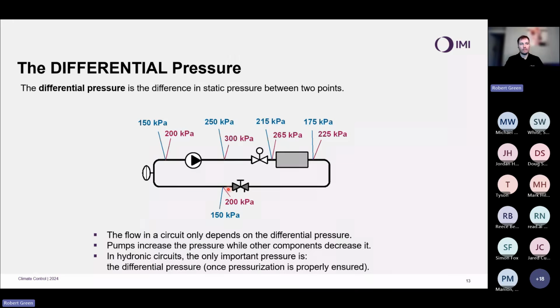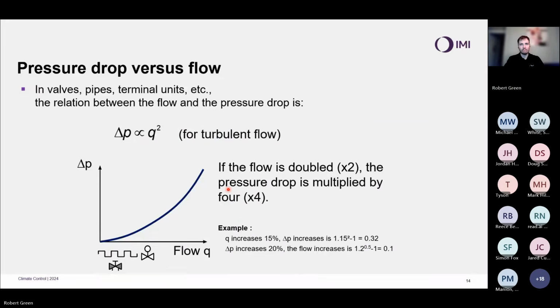But how does it drive flow? What is the relationship between flow and differential pressure? That's what we look at here. If we take pressure drop versus flow, in valves, in pipes, in terminal units, the relationship between the flow and the pressure drop for a turbulent flow, which when we are talking HVAC systems at design conditions, which is what we're balancing to, we should have turbulent flow throughout the system. It should have been designed and sized correctly for turbulent flow. The differential pressure is proportional to the square of the flow.